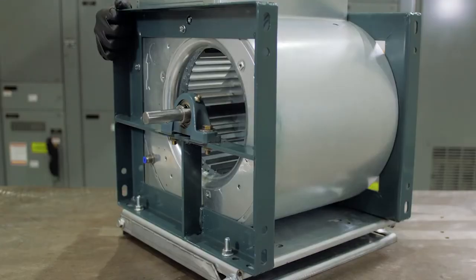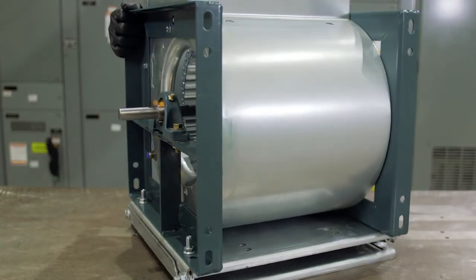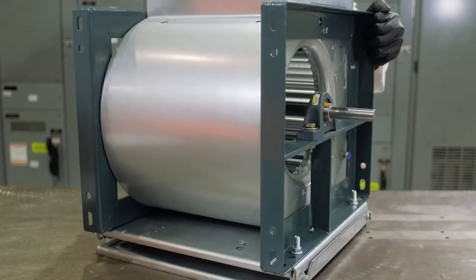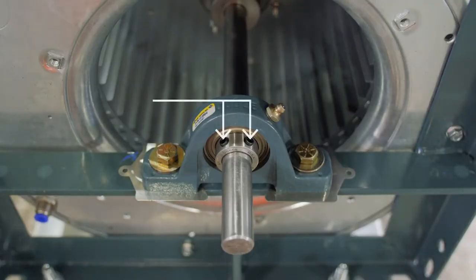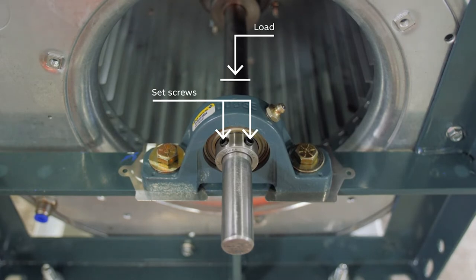The next step is to fasten the bearings to the shaft. To minimize unbalance in the system, position the set screws for each bearing in the same location radially. Set screws should be tightened in the same direction that the load is acting. Failure to do so could result in insufficient holding power.